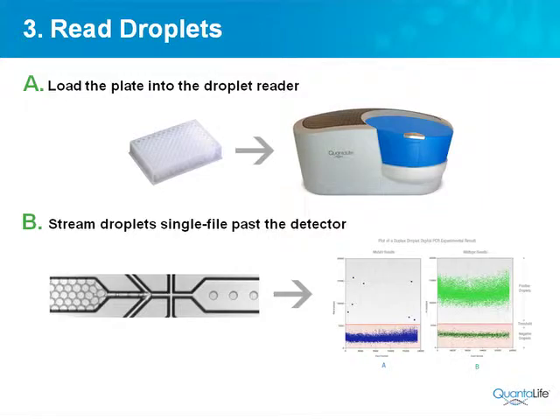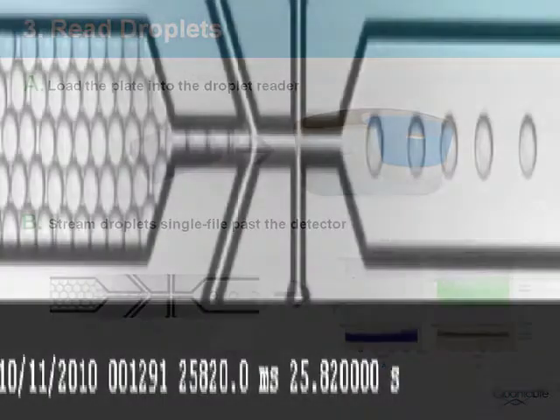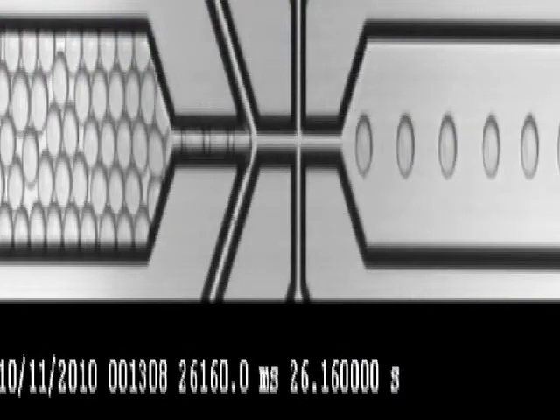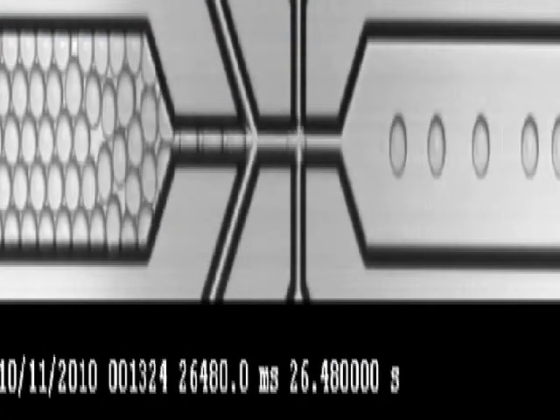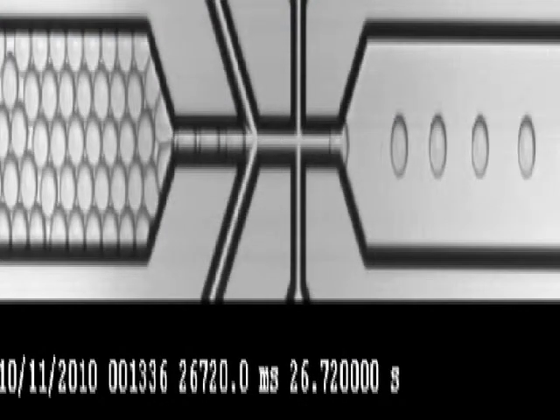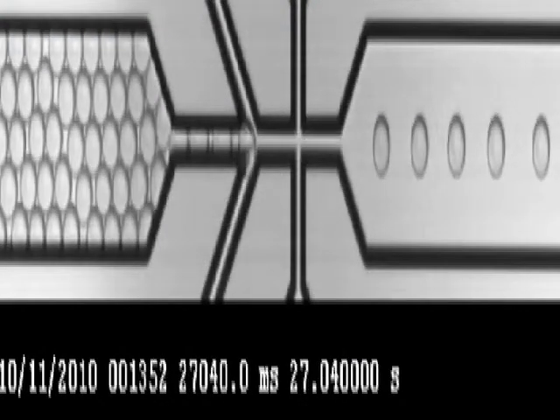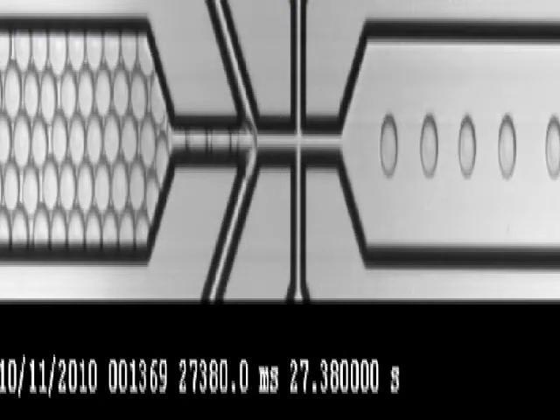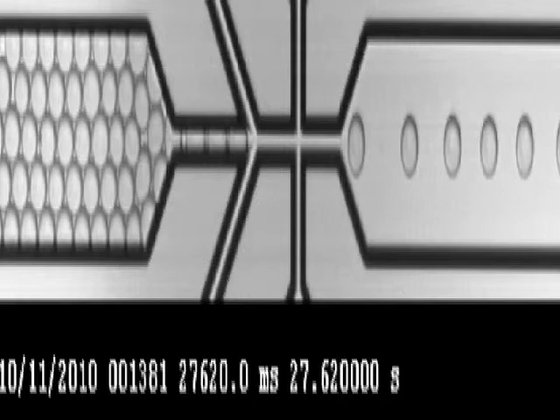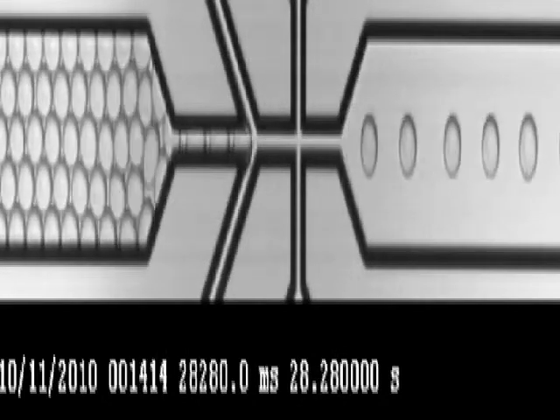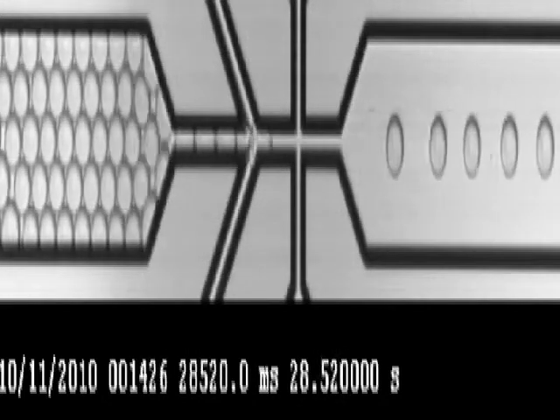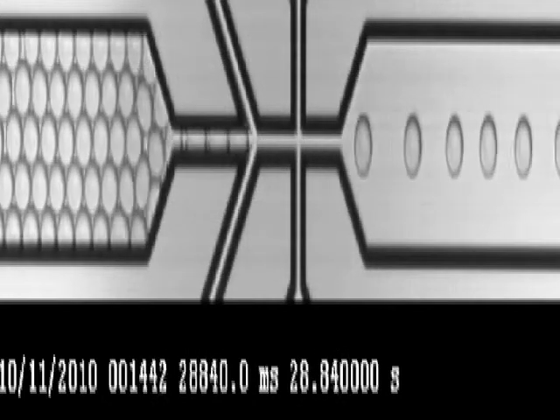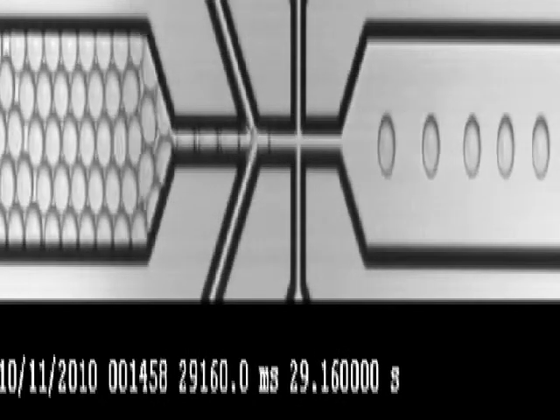It picks up the droplets one at a time. They start out packed and then it streams them past the detector. This is what's happening here — single file — and the detector then scans them on two channels: FAM and VIC for fluorescence.